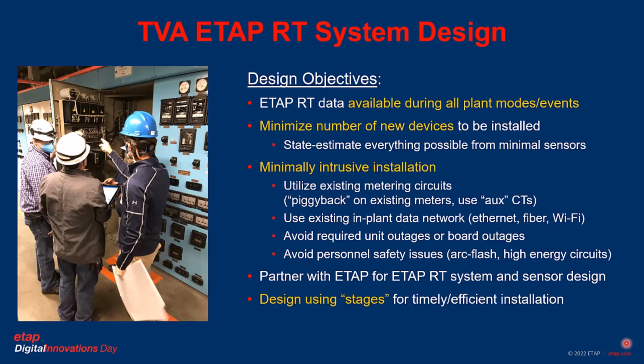sort of think about it as piggybacking over the existing meters, using things like auxiliary CTs to avoid breaking into a circuit, and using our existing plant data network. We have Ethernet, fiber, and Wi-Fi running through the areas where we will be putting these sensors. Avoid required unit outages or board outages to the extent practical, and avoid personnel safety issues. So avoid having to do an installation where you would be putting workers in harm's way, for instance, being around high energy circuits or creating an arc flash event. Try to focus on installing these sensors in metering compartments and relay compartments where it's all low energy circuits.